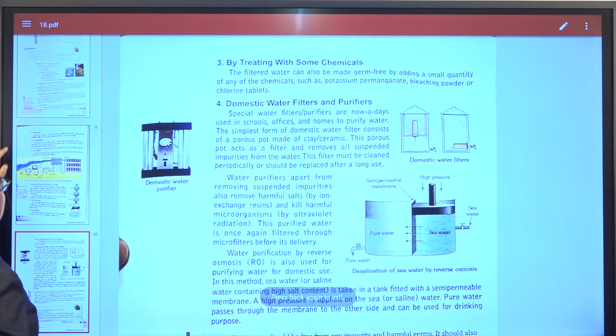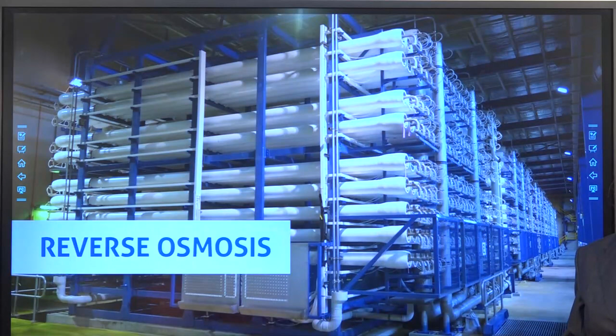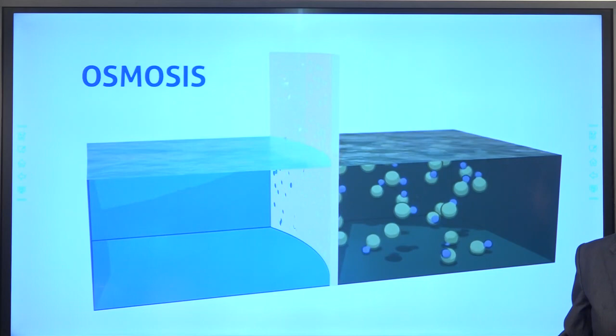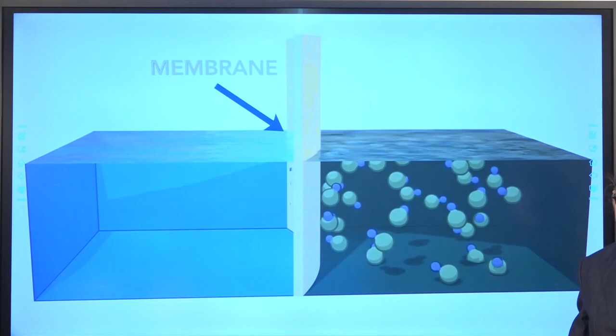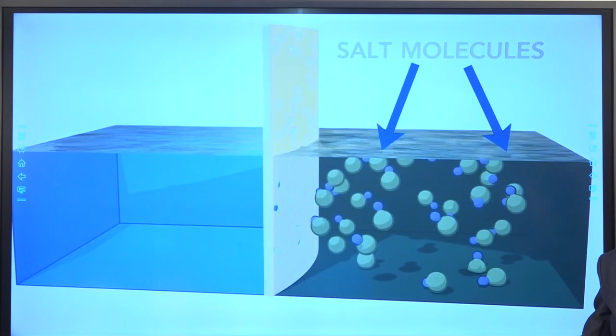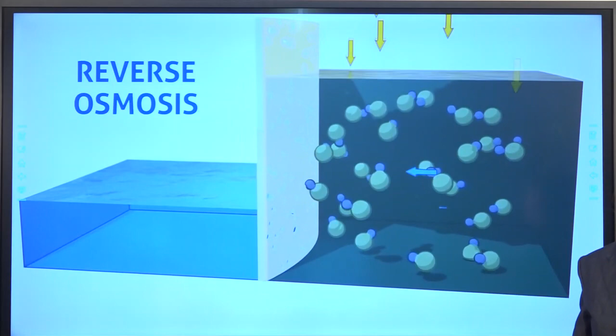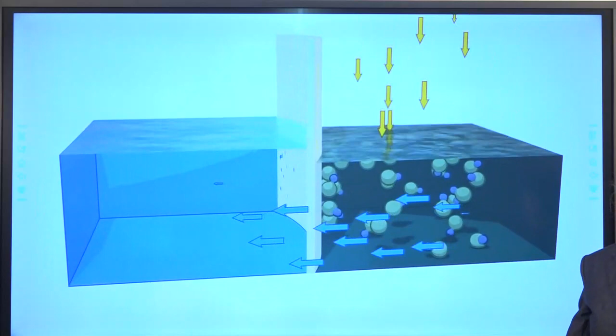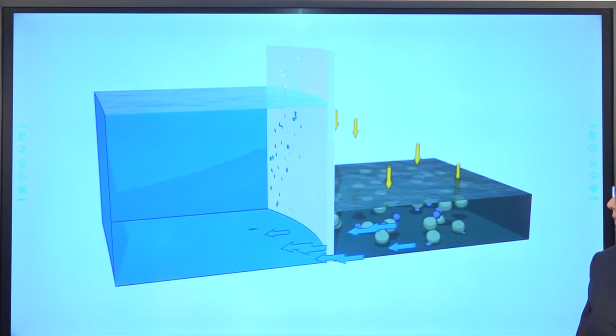This is the entire reverse osmosis process. Small one. The core technology used at the Adelaide desalination plant is called reverse osmosis. First, let's explain what osmosis is. Osmosis is a naturally occurring process in which a liquid, such as water, spontaneously passes through a membrane. The membrane or semi-permeable barrier allows some molecules, like water, through, but other molecules, like the majority of salts, are unable to easily pass through the membrane structure. The flow of liquid through such a membrane occurs naturally to try and even out the salt concentrations between the two solutions. That is, a liquid flows from the less concentrated solution, such as fresh water, to a more concentrated solution, such as seawater. When the direction of liquid flow is reversed, it's called reverse osmosis. By pressurizing the concentrated solution, in this case seawater, we are able to force water molecules in the reverse direction, from the salty seawater side through the membrane to the freshwater side.